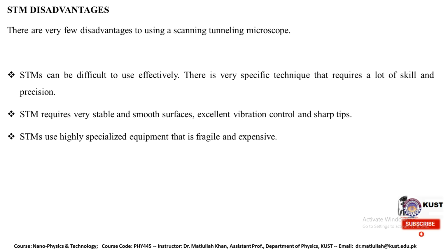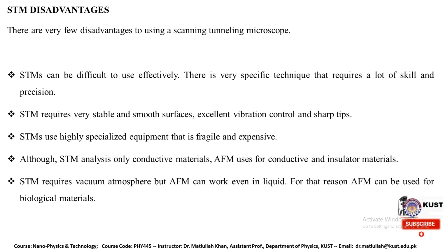STM requires very stable and smooth surfaces and excellent vibration control, because these piezoelectric components are used here, so the system must be placed on an excellent, smooth surface so that there is minimal or zero vibration affecting the other parts of the system. STMs are highly specialized equipment that is fragile and expensive compared to other systems.